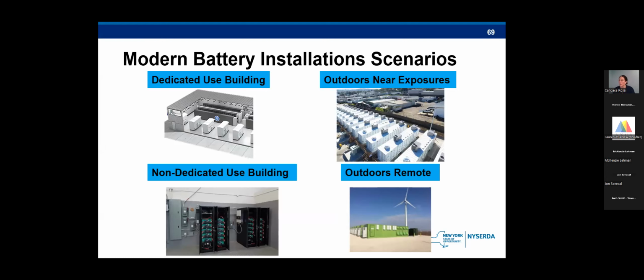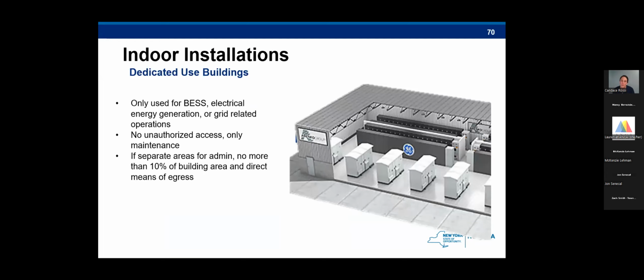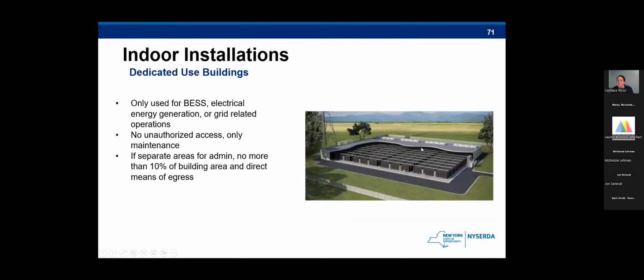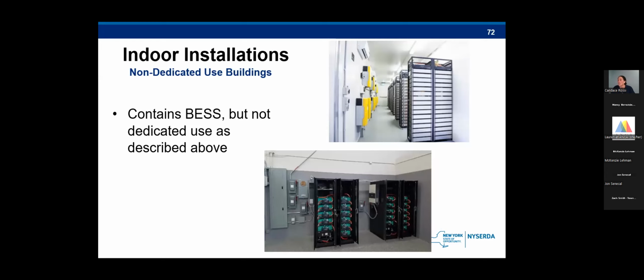So this is just a quick overview slide of some of the different locations we're going to talk about and how the requirements differ. So first we have the dedicated use building. So these are only used for the purpose of housing an energy storage system or any grid related operations. Only admin personnel can be within the building, but the area that can be used is limited to 10% of the floor space. So obviously this is a building only for energy storage, really nothing else. And then here is another example of what an extremely large dedicated use building may look like. And then the other type of indoor installations are what's called non-dedicated use buildings. So some examples of this could be colleges, work centers, residential apartment buildings. And this slide is just showing pictures of a few systems installed in mixed use buildings.